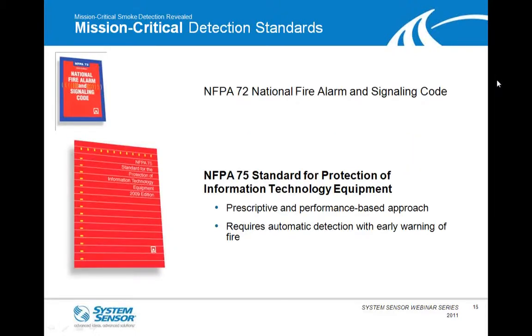The second code, again, we're going to go into these in more detail, is NFPA 75. This is the standard for protection of information technology equipment. This code, in just general terms, offers prescriptive and performance-based approaches. It also requires automatic detection with some sort of early warning of fire. Now, again, just because it calls out for early warning, a lot of people jump to the conclusion that aspiration is required.